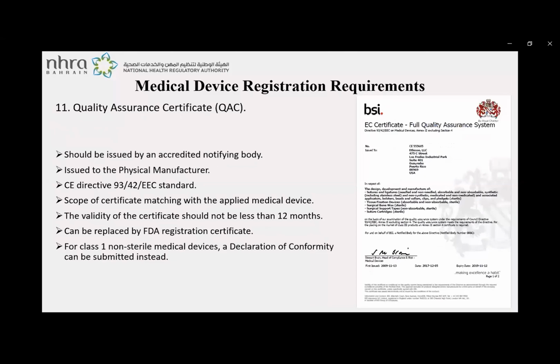Number 11 is the quality assurance certificate. This certificate is needed to certify that the medical device quality and safety is in conformity with medical devices international standards, in which NHRA accepts CE Directive 93/42/EEC, which is for medical devices. This certificate needs to be issued to the physical manufacturer with the same address. Unlike the QMS, it should be issued by an accredited notifying body. Its scope should match the applied medical device and should have a validity of at least 1 year.